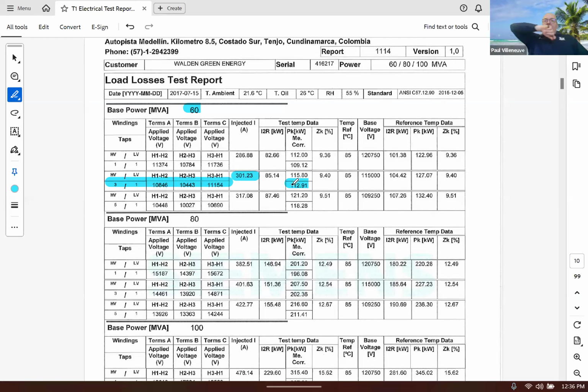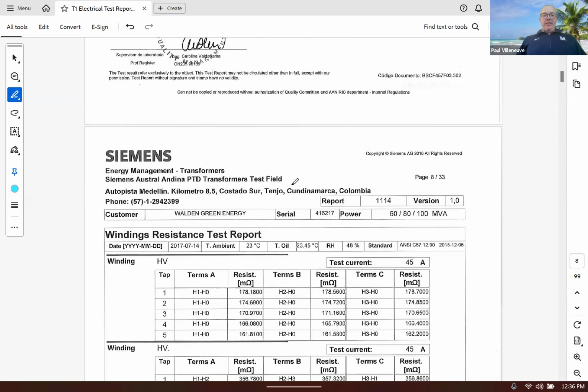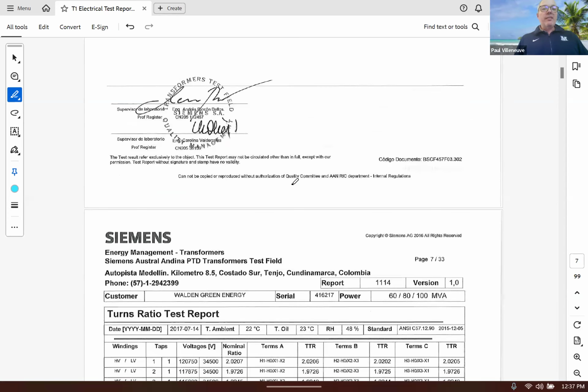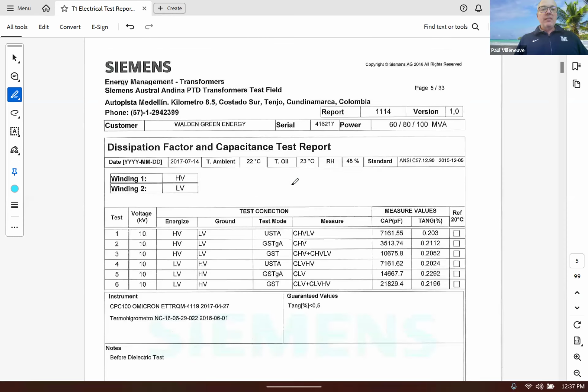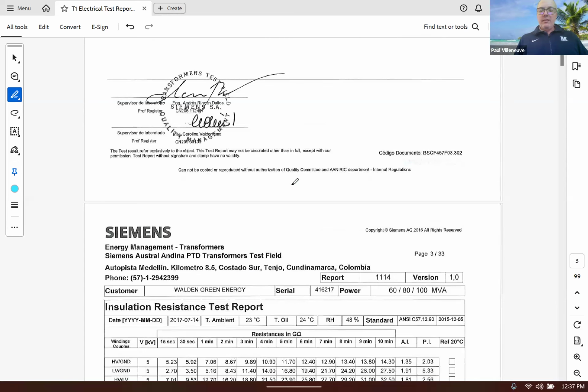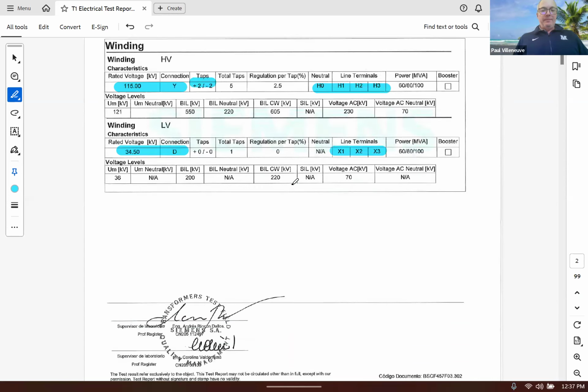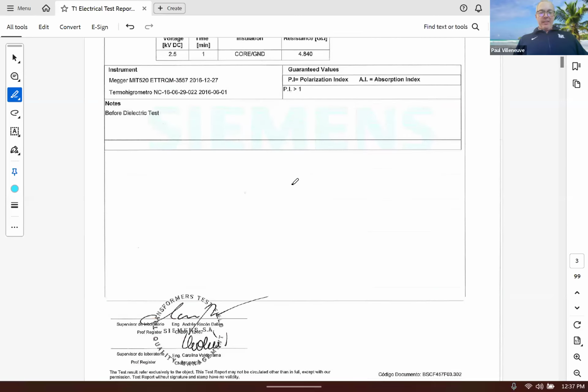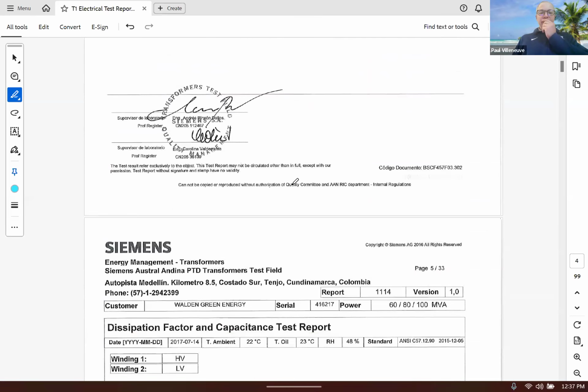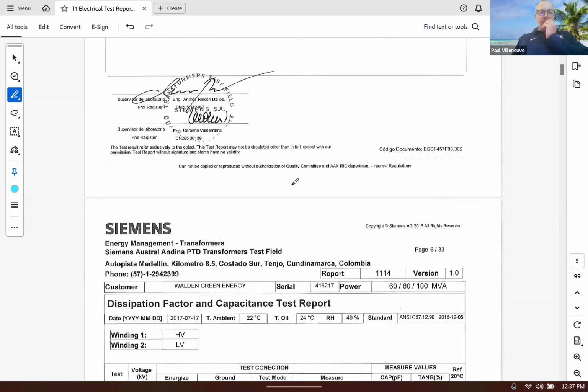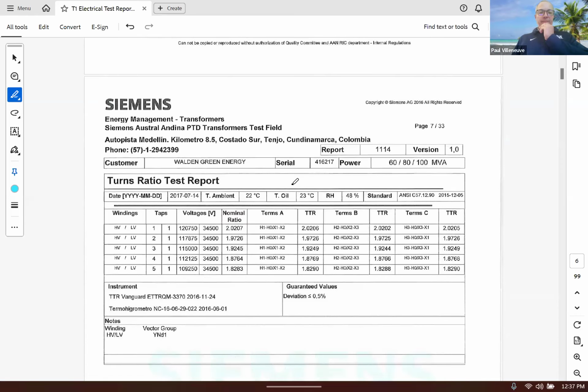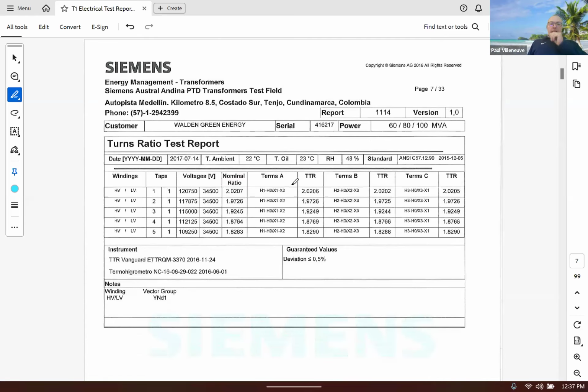Okay? I have a question. Yes. Because it tells me it's tap position 3, right? That's in the intermediate tap position. So that's where I know it's the 115 kV. You can also go up over here and you can even see winding resistance, turns ratio. And then I go past it. It should tell me the tap positions too. 1, 2, 3, 4, 5. Let's see if I might not have had it up on the screen. No, I'm getting closer. Okay, so if you see here, you see tap position 3. What do you notice? The voltages are exactly the nominal voltages.